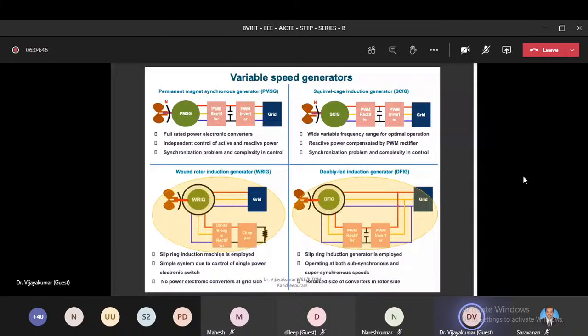But in a rotor resistance control method, the machine takes power from the grid and operates as a motor. Then by varying the resistance, you are controlling the speed of the machine in the drives, right? How do you vary the resistance? Just by varying the duty ratio of the chopper. By varying the duty ratio of the chopper, the equivalent resistance in the rotor windings will change, so that we can control the speed of the generator, right?